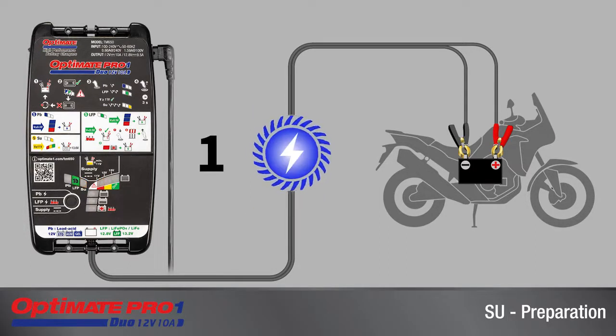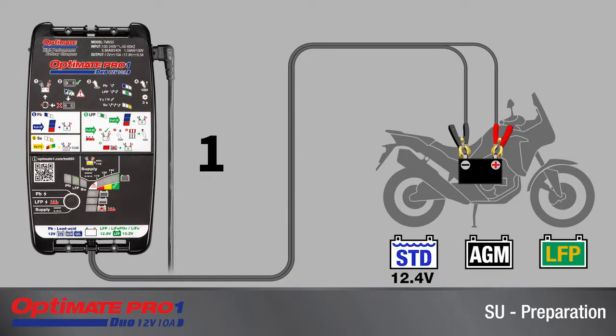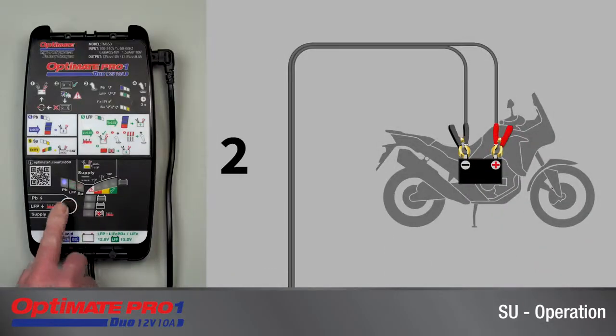The battery should be charged before using the supply mode as a diagnostic support. A sufficiently charged battery should retain 12.4 volts or higher for a standard wet cell battery, 12.6 volts or higher for a sealed AGM, and 13.2 volts or higher for a lithium battery. To select the power supply mode, press and release 3 times. Only LED 2 should be lit.